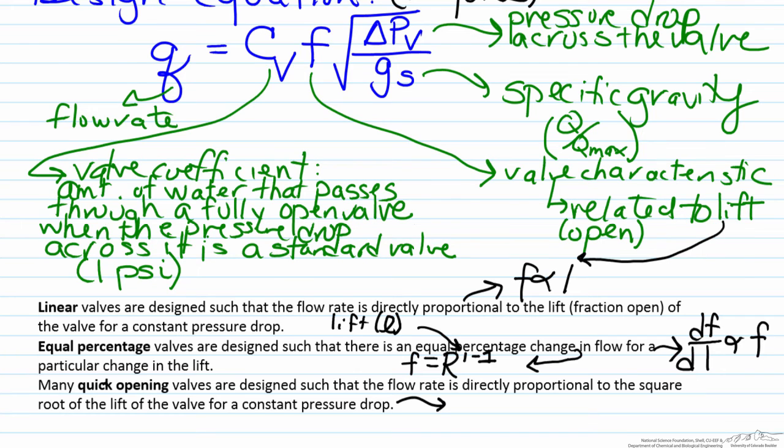Quick opening valves are done such that the valve characteristic F is related to the square root of the lift. For a quick opening valve, as the name indicates, when we open the valve very slowly a lot of flow comes out. Therefore these valves are designed such that at low flow rates you get more of the flow coming out, and then when the valve gets more open you get diminishing returns on it.